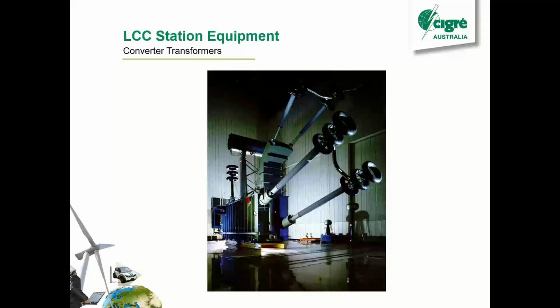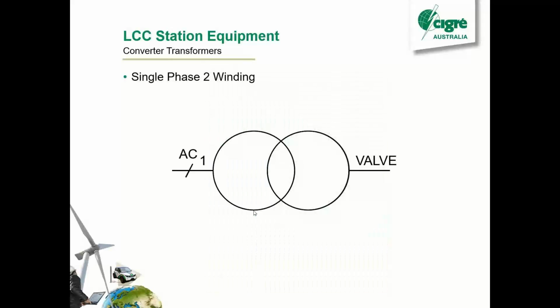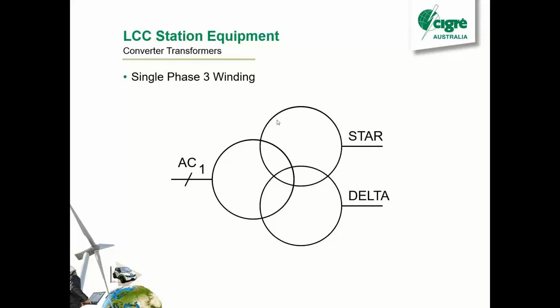So there's a few different configurations you can have for your converter transformers. You can do single phase 2 windings, so that's when you have single phase transformers and 1 valve winding. With this configuration, you would need 6 converter transformers per pole to get your 12 pulse converter. The other way is single phase 3 windings. You can feed the whole 12 pulse converter per phase with 1 transformer. This is what we've got in New Zealand. So there's 3 converter transformers per 12 pulse group with this arrangement.